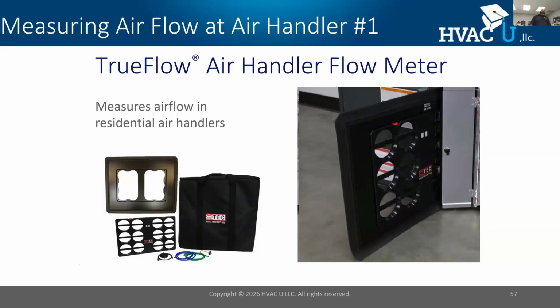Real popular now is direct flow measurement using a flow plate. The way it works, we take static pressure measurements, then remove the air filter and put in this flow plate. It takes the static pressure measurements we had, retains the pressure drop of the filter, then measures flow and interpolates what the airflow of the system is. Really awesome tool to get airflow and static pressure really quick.